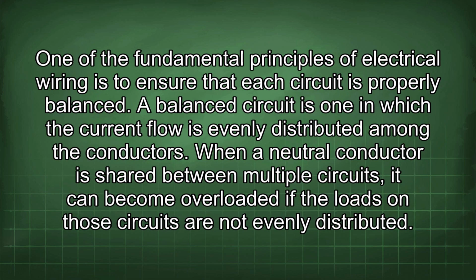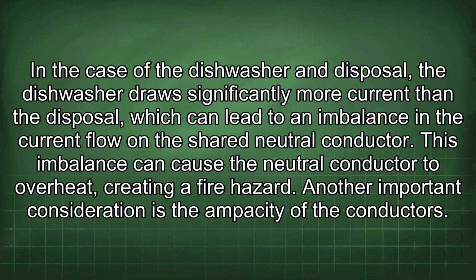One of the fundamental principles of electrical wiring is to ensure that each circuit is properly balanced. A balanced circuit is one in which the current flow is evenly distributed among the conductors. When a neutral conductor is shared between multiple circuits, it can become overloaded if the loads on those circuits are not evenly distributed. In the case of the dishwasher and disposal, the dishwasher draws significantly more current than the disposal, which can lead to an imbalance in the current flow on the shared neutral conductor. This imbalance can cause the neutral conductor to overheat, creating a fire hazard.